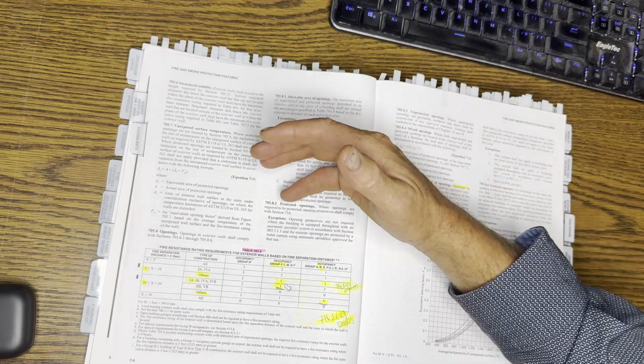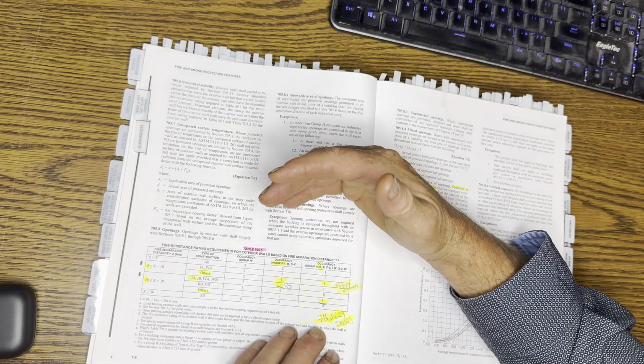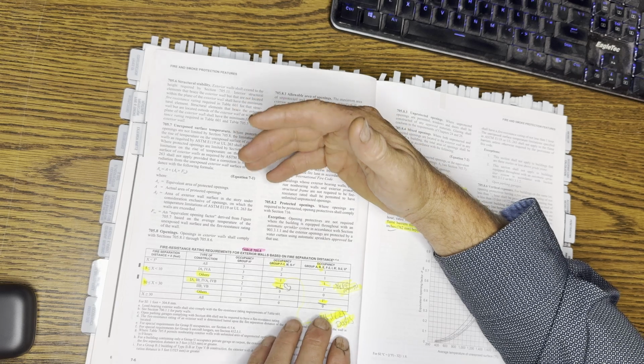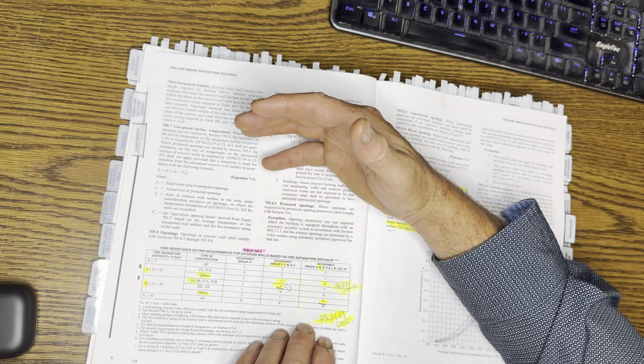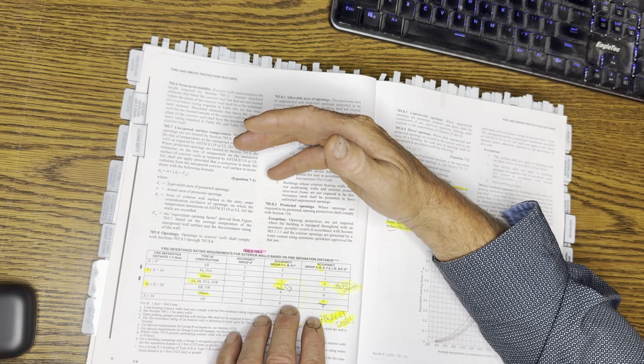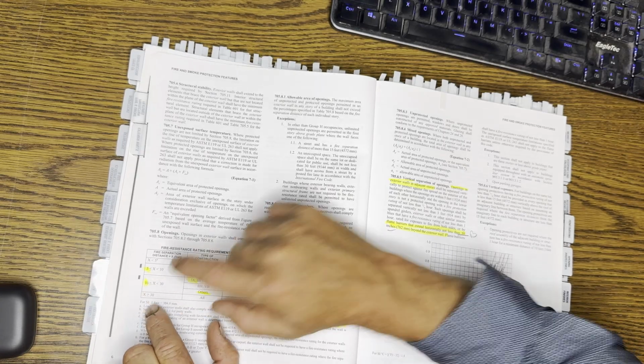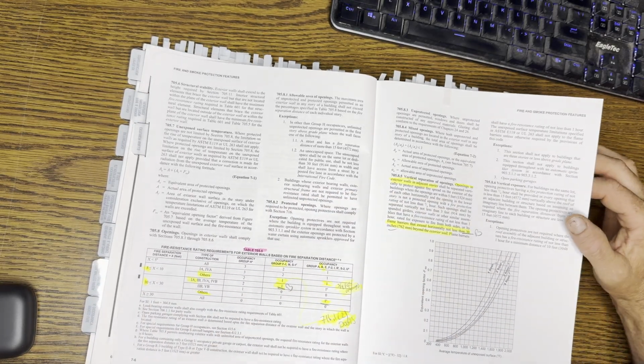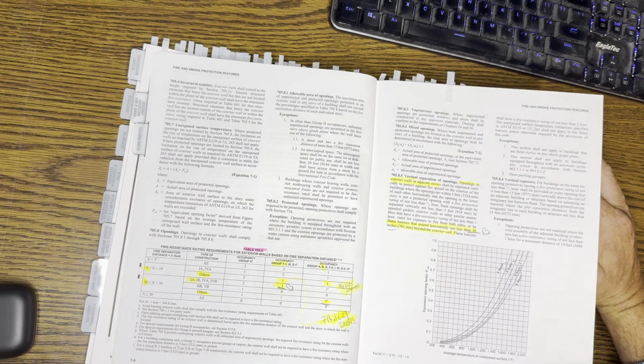So they'll ask, let's say two buildings, how far do two buildings have to be away? Two Type 2B buildings have to be away so the exterior walls do not have to be fire rated. And the answer would be 20 feet because you got to double that. It's that kind of thing. Just be aware of that. It's a tricky table, and a lot of people make mistakes on that table.